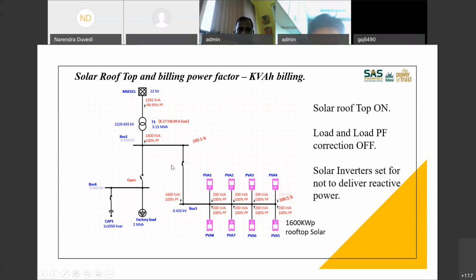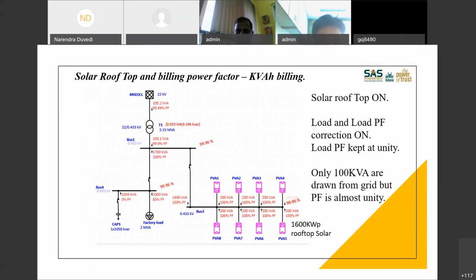If you disconnect this, then it will not go there. But if you keep this connected, and if you are not using it locally, your power has to go back to the grid. Again, here you are pumping in only active power, because your solar plant is generating only active power, and your power factor is again 99.95%. So the power factor will not change even in this case. Now let us see the third case.